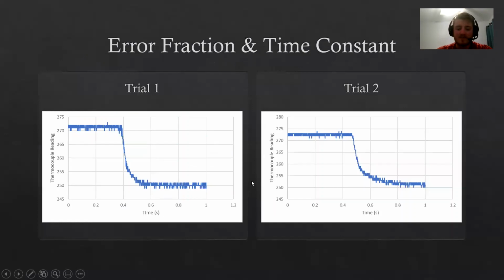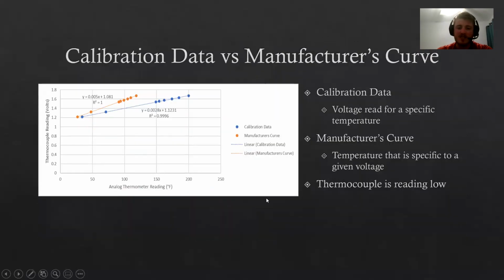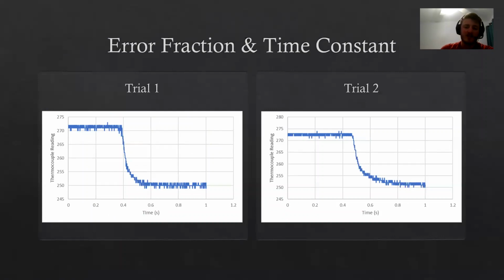The error fraction. This test was done by dipping the thermocouple in water, starting the test just so we can know what the thermocouple is reading for that temperature. This is done by starting the test while the thermocouple is in air and then dipping it in water that is a different temperature. So we can see the ambient temperature here, and then there's a sharp decline where it changes, and then into the freezing water temperature. This is to determine the error fraction and the time constant.